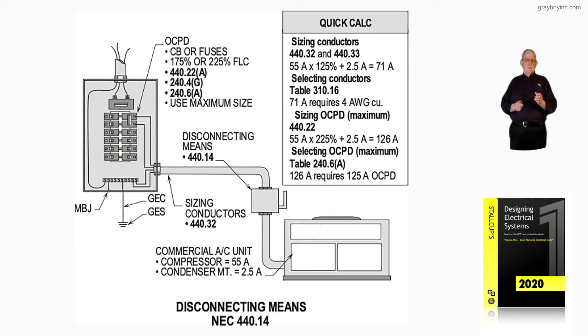This illustration deals with disconnecting means for an air conditioner in accordance with 440.14. Notice the overcurrent protection device ahead of that branch circuit could be sized at 175% all the way up to 225% of the full load amps or current. That's per 440.22(A).